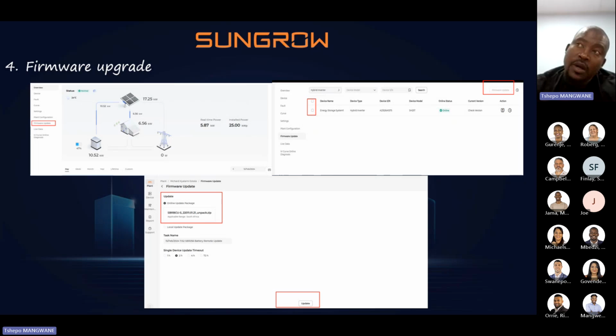So now we are on firmware upgrade. We only do a firmware update if the installer is missing one of the parameters. If you log in to the local access point, you can find your grid settings, your compulsory mode settings. Then we know that the firmware of the system is outdated, or the system is malfunctioning. Then we can do the firmware upgrade on the system.